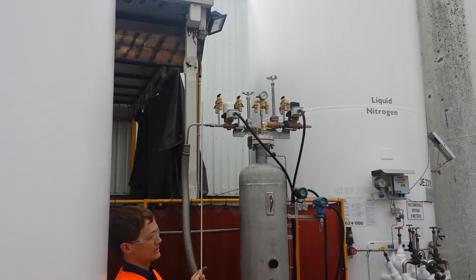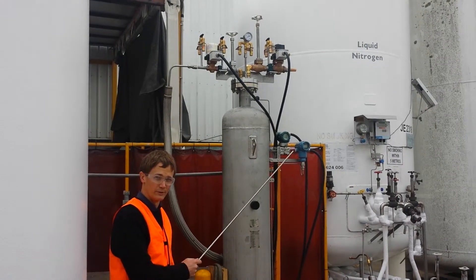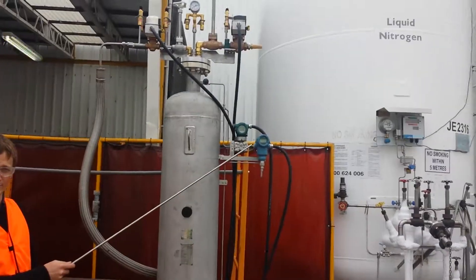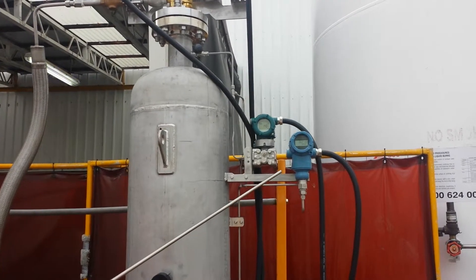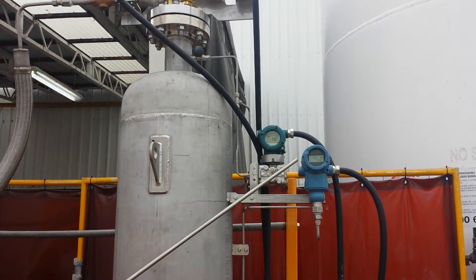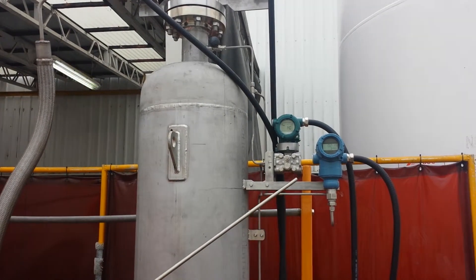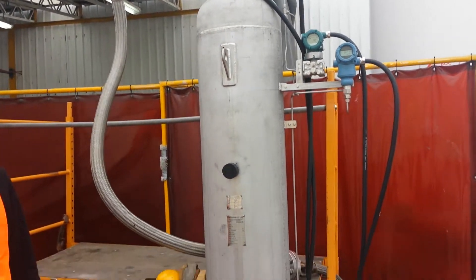In the various sections over here we have our instruments. We have a level transmitter with gauge and a pressure transmitter with gauge. This is also a special order CryoBuddy — the standard one won't have the display on the pressure transmitter; it'll just have a small pressure transmitter without display.